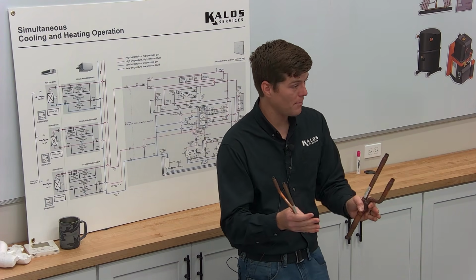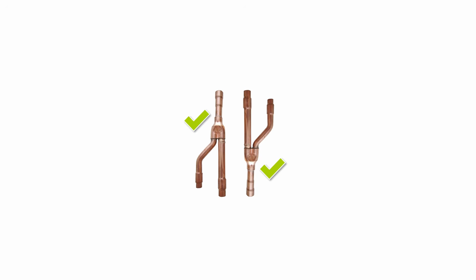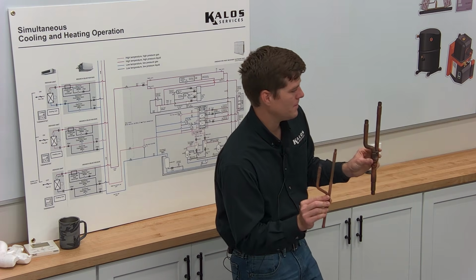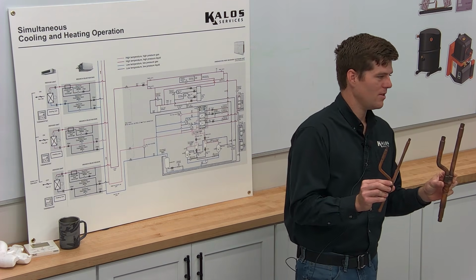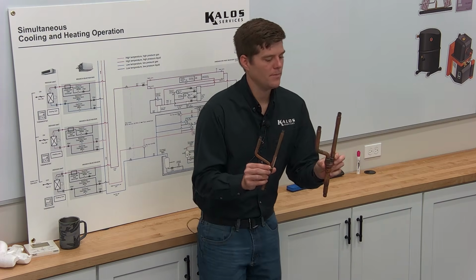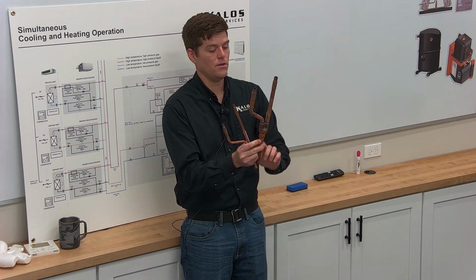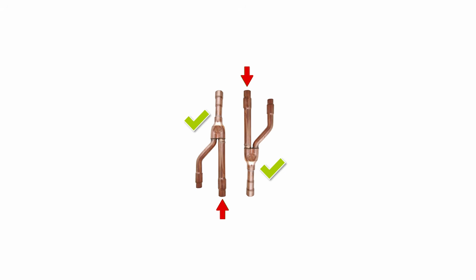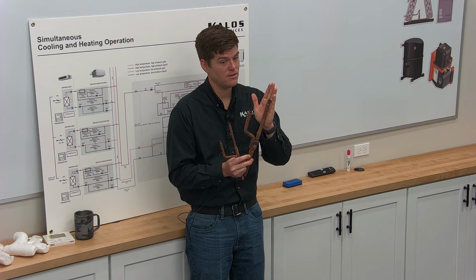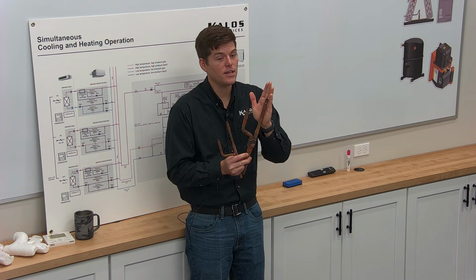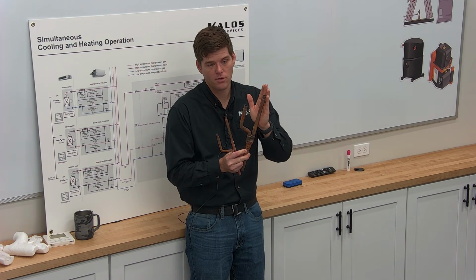based upon which one might be calling. You'll notice that they look a little different, right? They're a little shorter on one side than the other. Anybody want to take a guess why that is? Equal volume. Yeah. You'll notice that this one on my left-hand side is the one that continues on my main line set. It's going to be the path of least resistance, because I've got other boxes to supply. I've got other fan coils to supply.